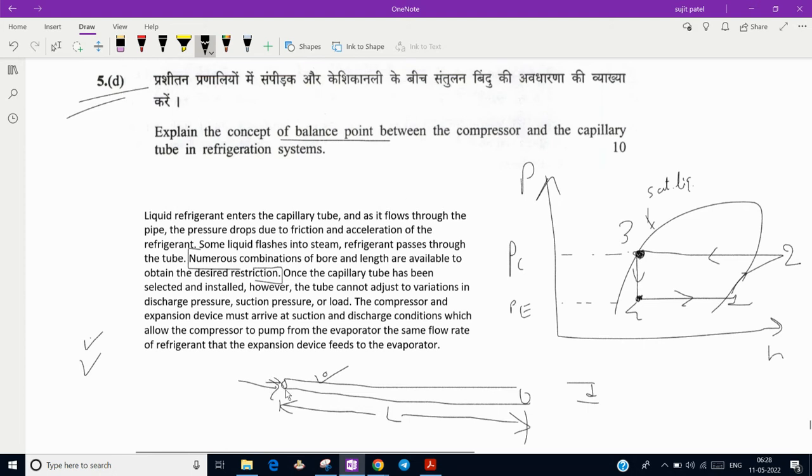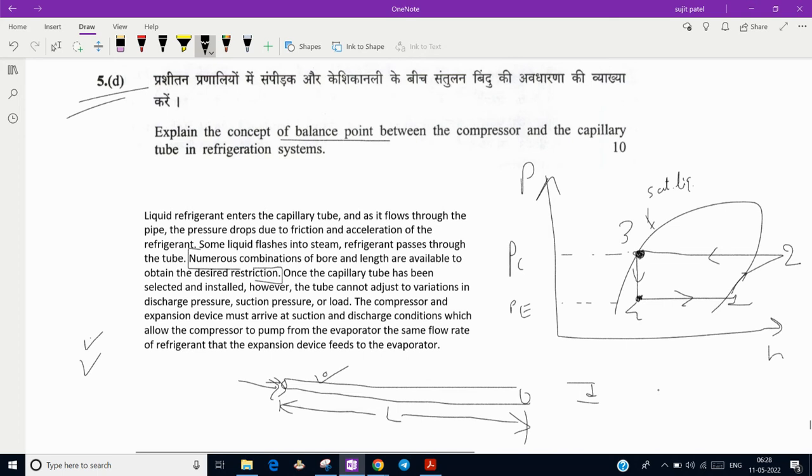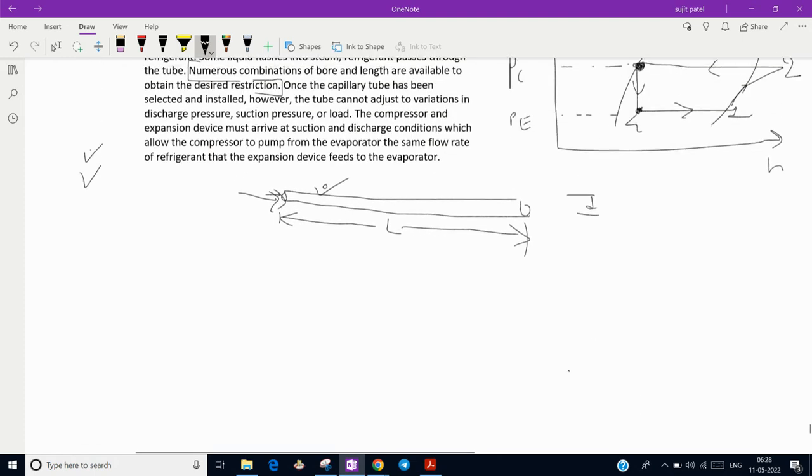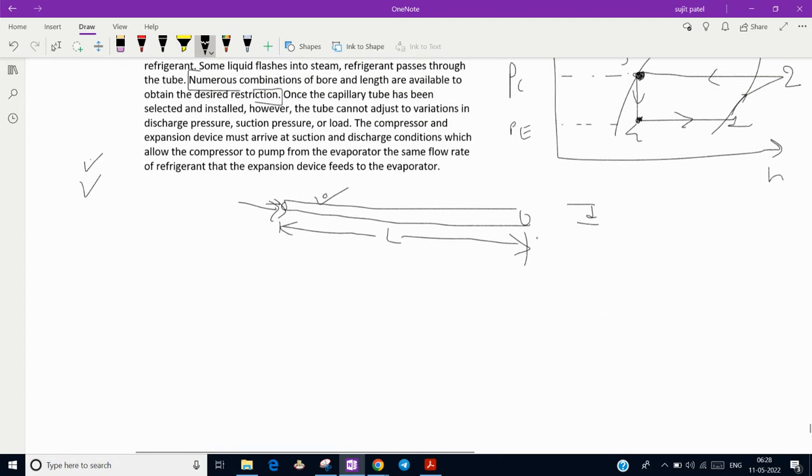Only fixed quantity of mass flow rate at fixed pressure and temperature will come in and out. The compressor and expansion device must arrive at suction and discharge conditions which allow compressor to pump from evaporator the same flow rate of refrigerant that the expansion device feeds the evaporator.